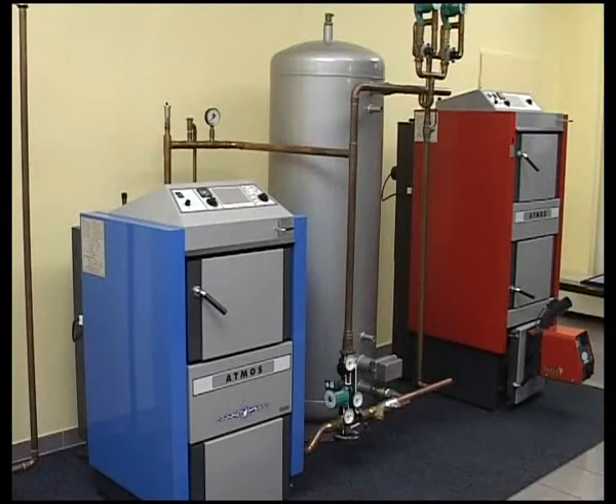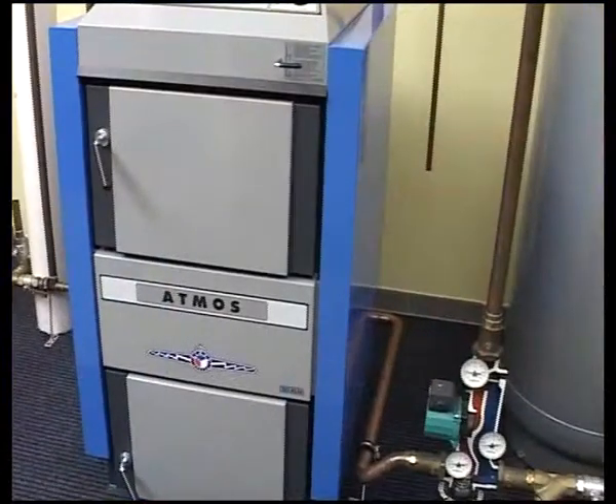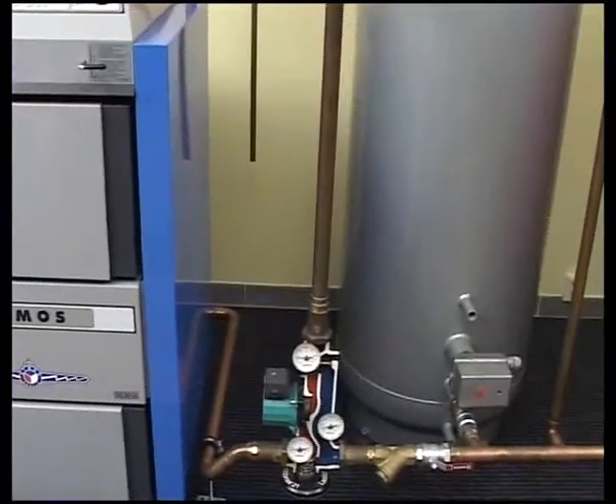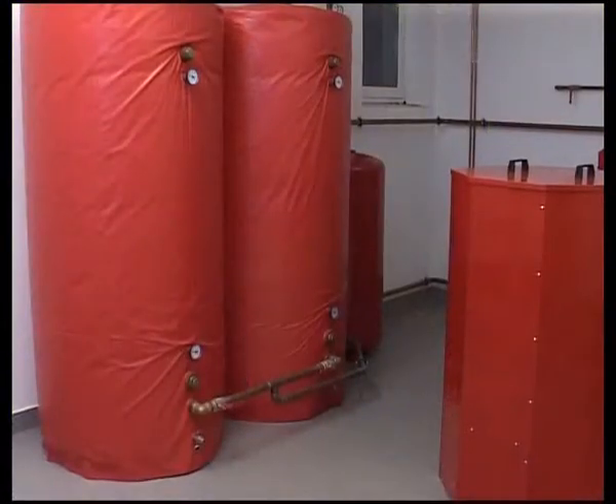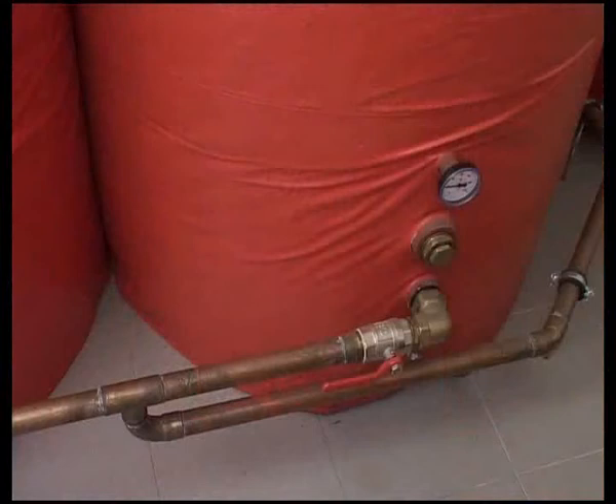Installation is most important for the service life and correct operation of the boiler. The best way to connect the boiler is with accumulation tanks and with the Laddomat 21 thermoregulator. This enables ideal tank charging and protects the boiler against low-temperature corrosion.